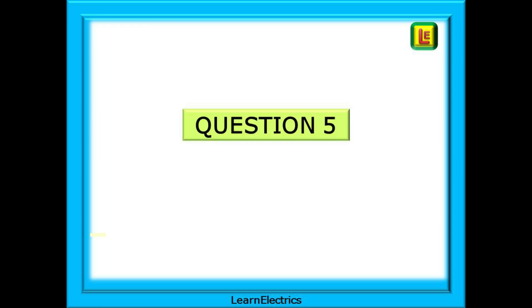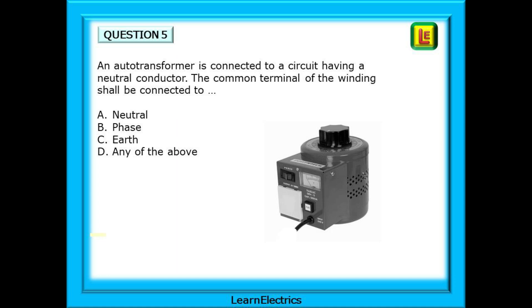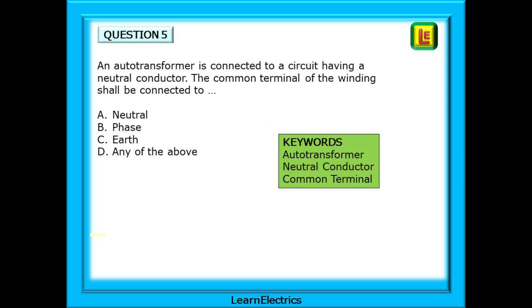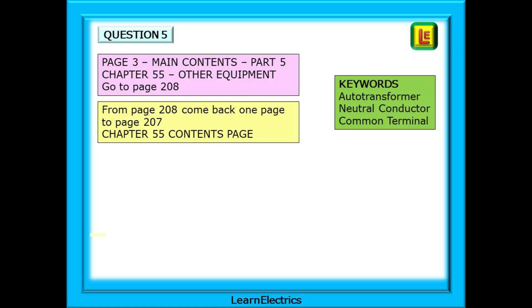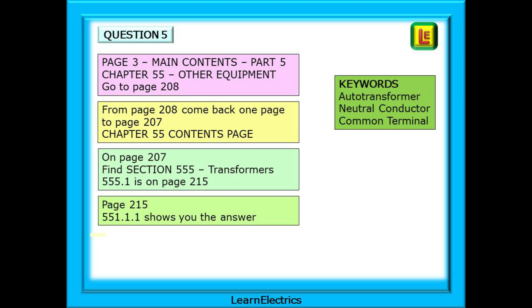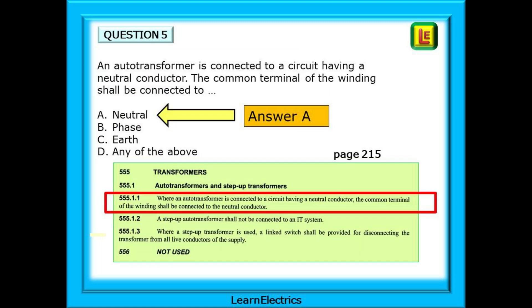Question 5, staying with other equipment: an auto transformer is connected to a circuit having a neutral conductor. The common terminal of the winding shall be connected to what? Go to page 3, find Part 5, then chapter 55, other equipment on page 208. Go back to page 207 for the chapter 55 contents page, and find section 555, 'Transformers.' Find 555.1 on page 215, then look at regulation 555.1.1 — this will show you the answer. We should choose answer A: the neutral.